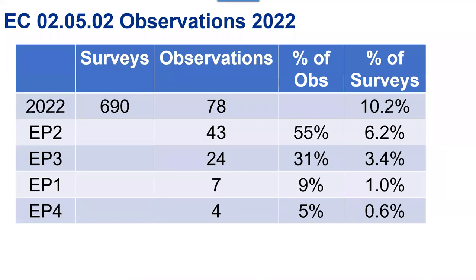Finally I'll share some data since we started the new standard in EP, for the first 6 months of 2022. I broke it down by EP so you can see where folks are having the most difficulty complying. The biggest thing that jumps out is the percentage of surveys with water management deficiencies is about 2.5 times what it was under the old standard. We were at about 4% before; now we're at about 10.2%. EP2 is the most frequently scored EP in that standard, with EP3 second.